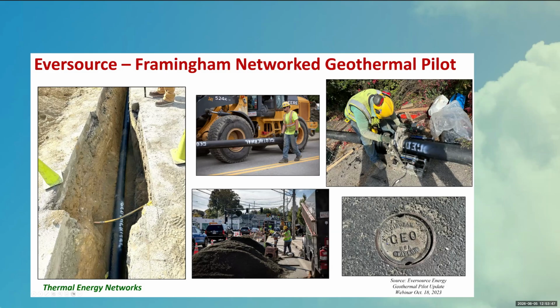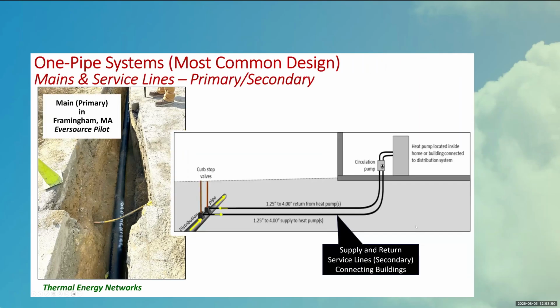Once it's all installed, you'll have some of these caps, which are essentially just curb stop valves. So with a supply and return connection to a customer's house—whether residential or commercial—if they ever need service or need to swap out a heat pump, they can shut off the water at the main. That way, if they get air in the system, it doesn't get into the main distribution pipe, which could cause issues down the road. It makes things easier to purge and take care of in the future.